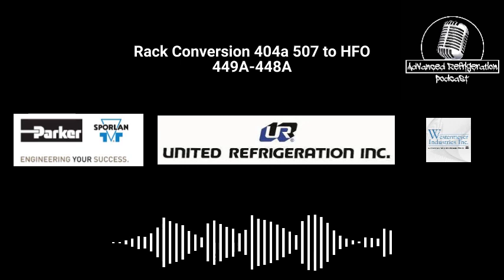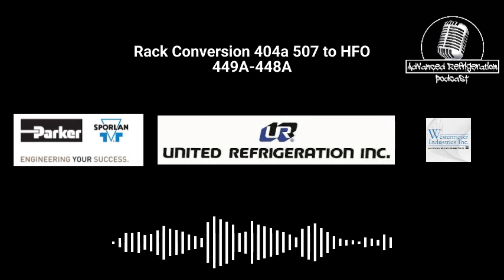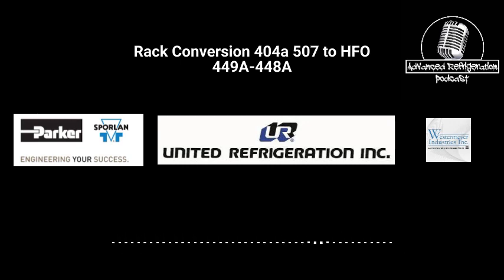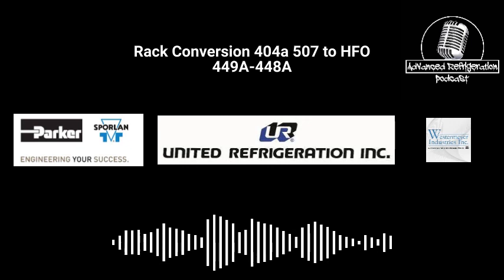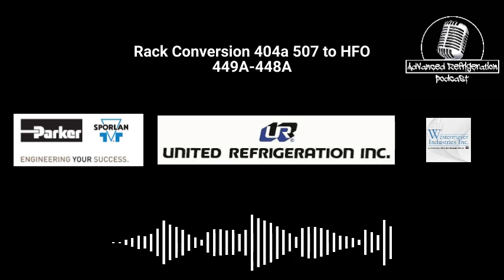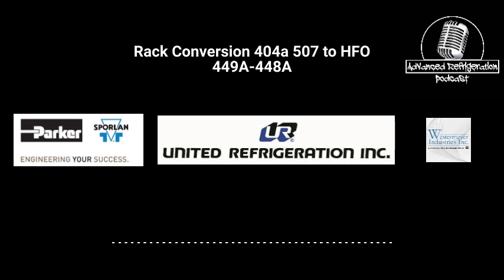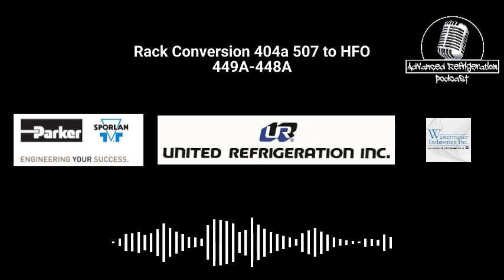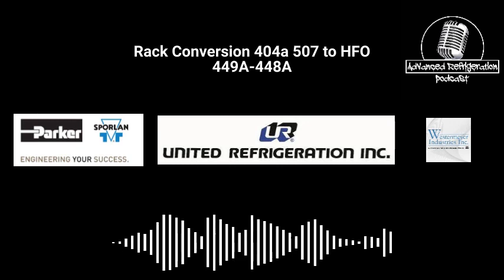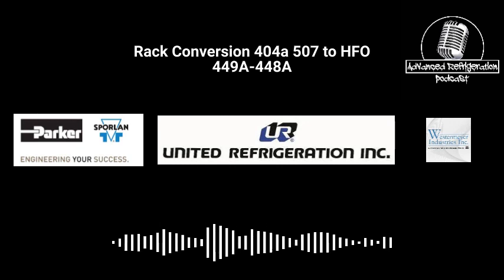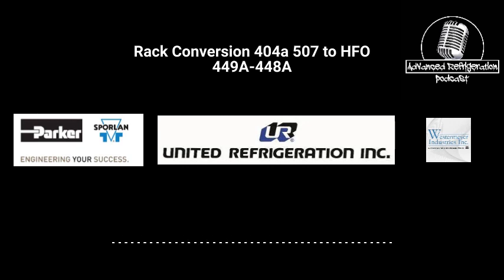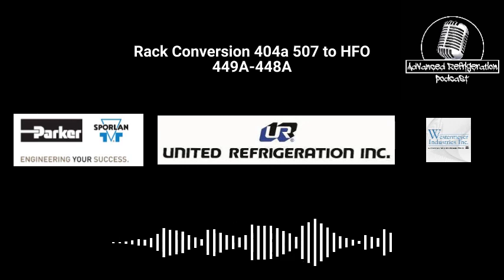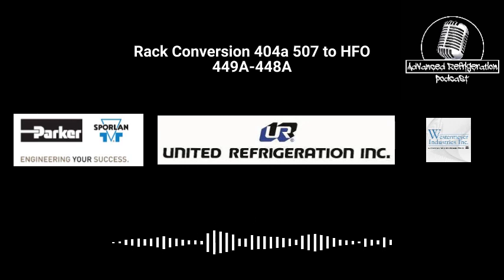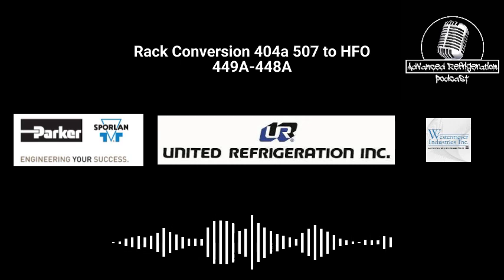So it becomes a problem panel mounting these. If they're doing it from the OEM it's fine, because they put them all in a row and leave a spot. But when you're retrofitting, it becomes a problem because you have to drill a 2.5 inch hole in the panel to fit it in, and there's a front plate that goes across it, so it's massive. If you need to put four of them in, you need almost 1.5 feet of space.